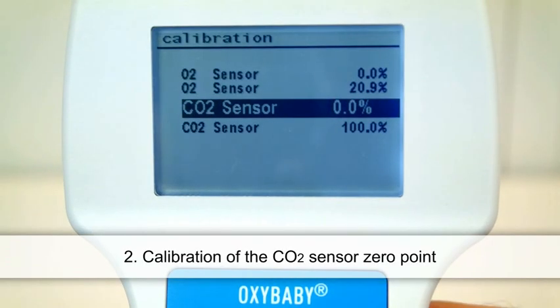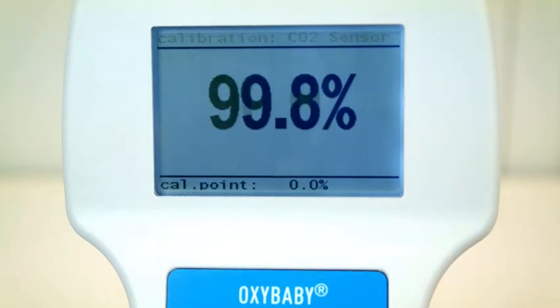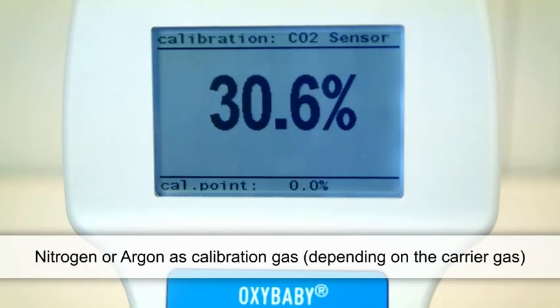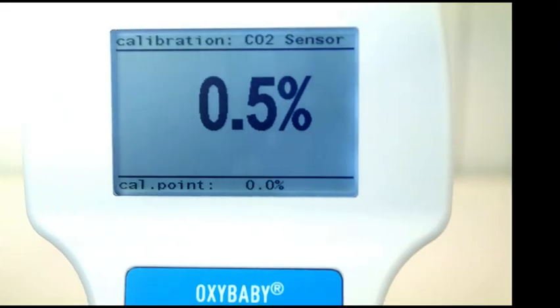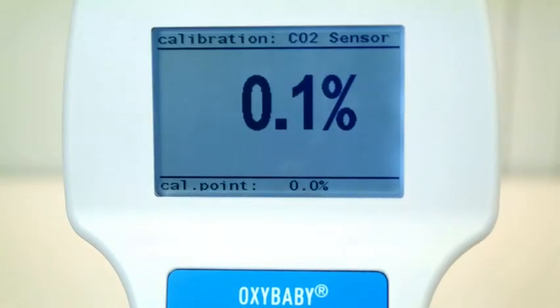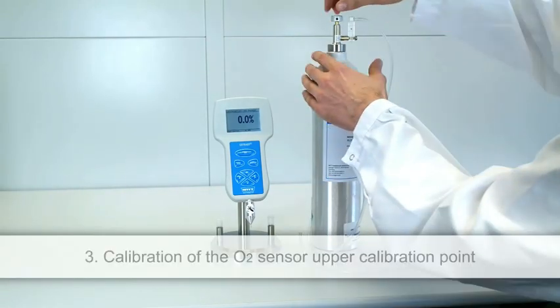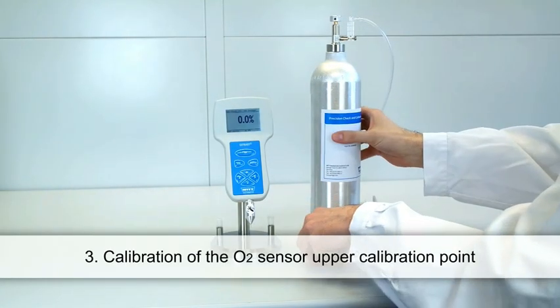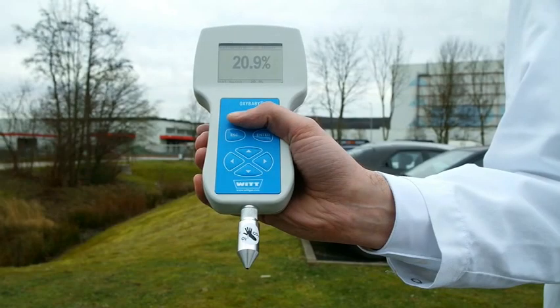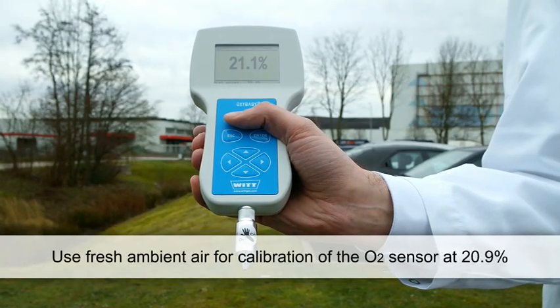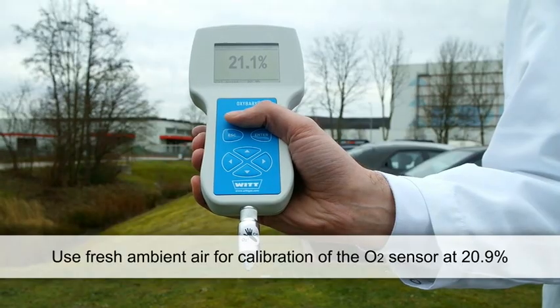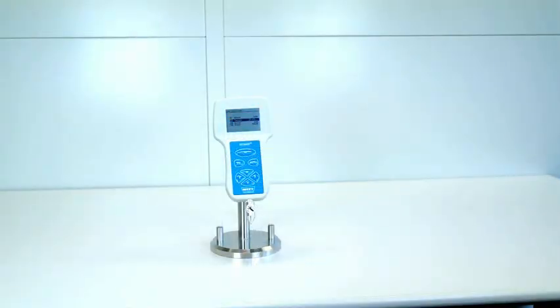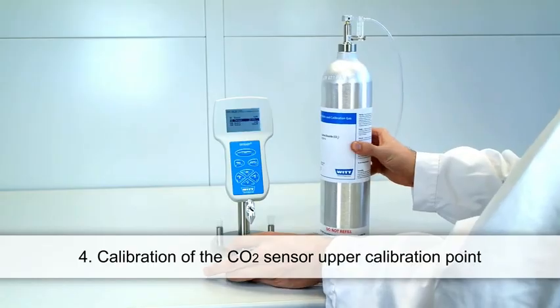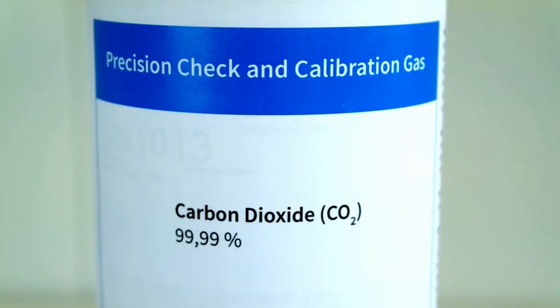The second step is to calibrate the 0 point of the CO2 sensor. As before, use a calibration gas that corresponds to your carrier gas, for example nitrogen or argon. After the calibration of the 0 points, you should calibrate the upper points of the 2 sensors. Start again with the oxygen sensor. Calibrate the Oxybaby for an upper calibration point of 20.9% simply by using fresh ambient air. In the last step, calibrate the upper calibration point of the CO2 sensor with CO2 as calibration gas. The CO2 calibration point again corresponds to your chosen CO2 calibration gas concentration, in this case 100%.